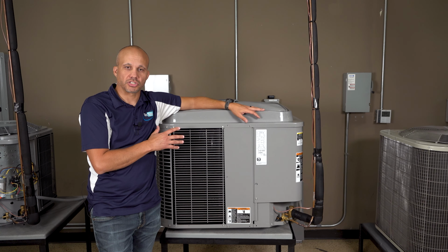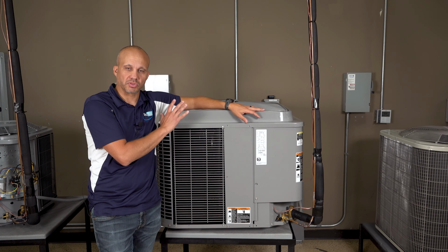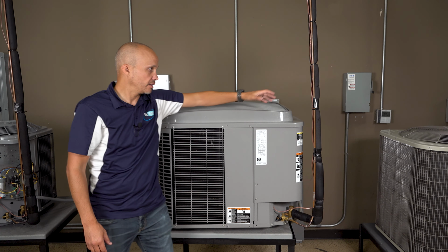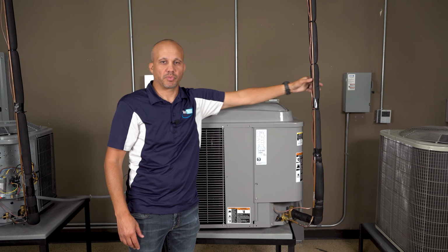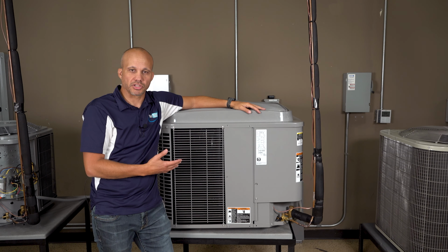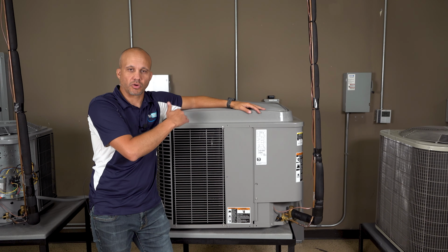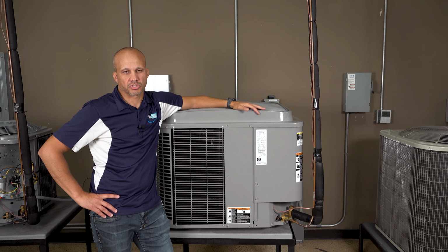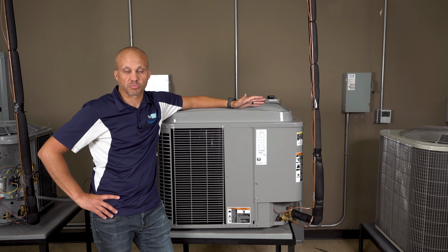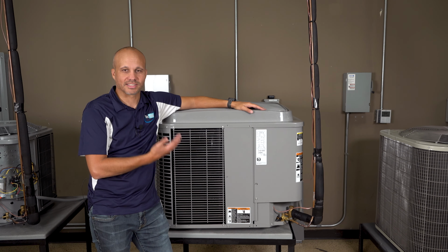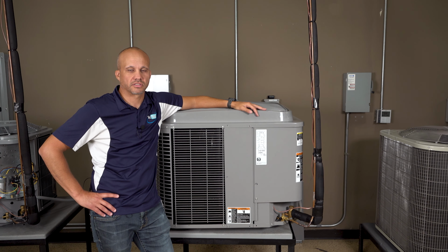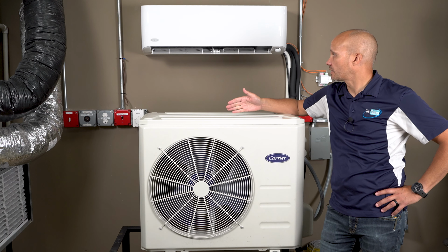Now, if this was air conditioning only, this would be the condensing unit with the condenser coil, and the indoor piece would have the indoor evaporator coil, and they're connected by two pieces of refrigerant piping. However, this is a heat pump, so as you already know, this is both a condenser coil and an evaporator coil. This one happens to be a 3-ton size, which is used in residential and small commercial applications, but it is scalable, and it can go up to maybe 130, 140 tons of capacity, which would be a much larger commercial building.